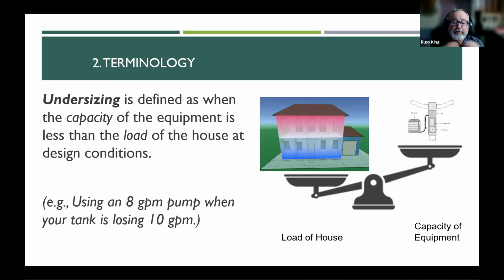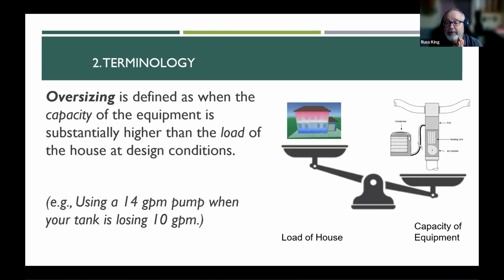Let's say, for example, using an 8-gallon per minute pump when your tank is losing 10 gallons per minute. You've got a tank of water and it's leaking 10 gallons per minute, and you're refilling it at 8 gallons per minute, the water level is going to drop, okay? There's a great analogy of a house being like a tank of water. So undersizing is when your equipment is too small. Oversizing is when your equipment is too big. It's when the capacity of your equipment is much greater than the load of the house, okay? That's like using a 14-gallon per minute pump when it's only losing 10 gallons per minute. So you're putting it in really fast, and then your water level starts building up, okay? So oversizing and undersizing, that's pretty straightforward.